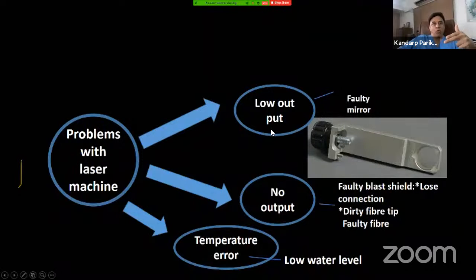If there is a very low output, the mirrors are faulty. And if the machine shows you a temperature error, you need to change the water. It is recommended that you read the manual, and according to the manual, you replace the water. But every 6 months it needs to be replaced, especially in a Holmium laser.